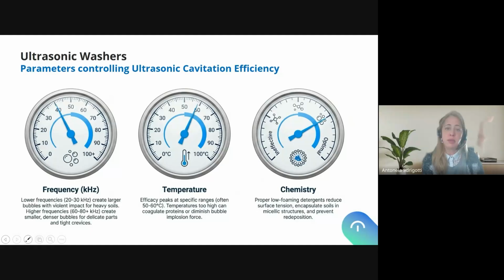So you can see that it's very important because depending on where my medical device will be located inside the ultrasonic washer, if the transducer at that location is not working correctly, the cavitation energy at that position will not be the precise that we need for the right cavitation energy to clean my instrument. So this is why it's very important to know how my ultrasonic washer is working. Generally, 40 kilohertz, between 35 and 45 kilohertz, is the normal working range of frequency of most of the healthcare dedicated ultrasonic washers. So that's the frequency at which transducers work.